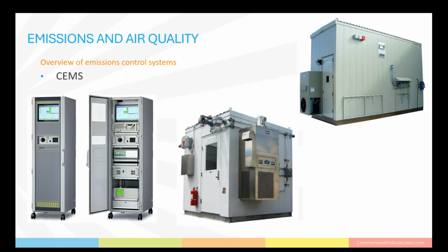The CEMS is made up of sampling probes, filter sampling lines, a means to condition the gas being sampled, a gas used for calibration, and a group of gas analyzers geared towards the gas being monitored. They're typically housed in a cabinet that sits at the base of the stack. And the CEMS unit can vary in size depending on the measurements required and the manufacturer.